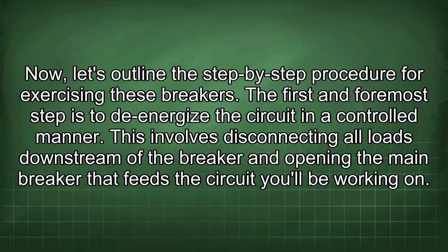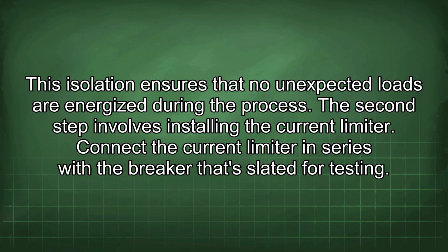Now, let's outline the step-by-step procedure for exercising these breakers. The first and foremost step is to de-energize the circuit in a controlled manner. This involves disconnecting all loads downstream of the breaker and opening the main breaker that feeds the circuit you'll be working on. This isolation ensures that no unexpected loads are energized during the process.